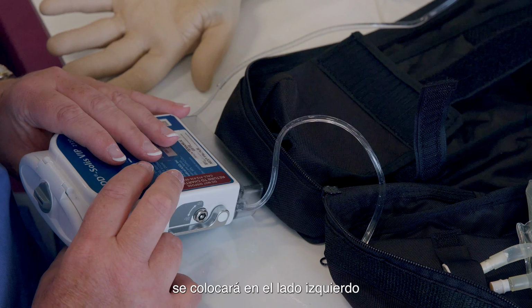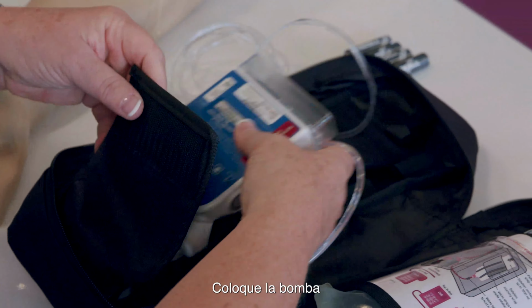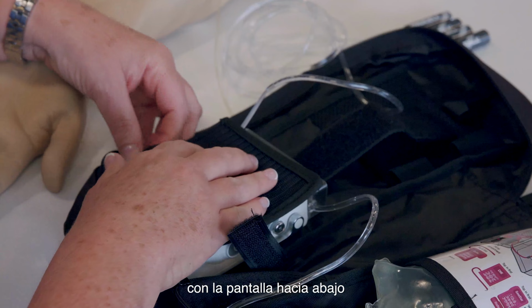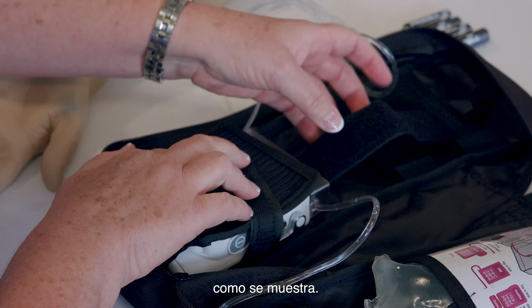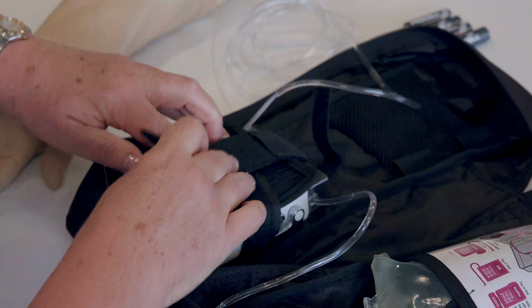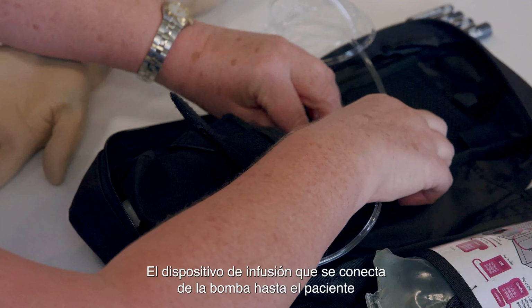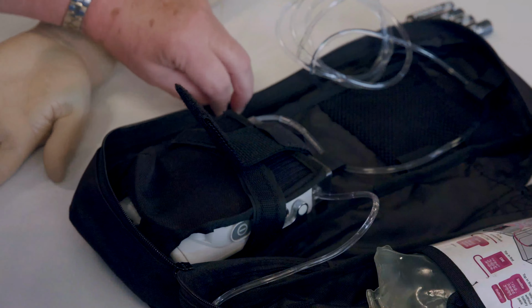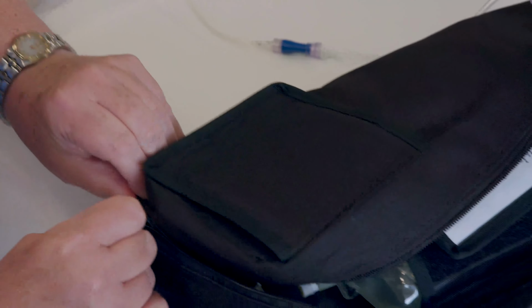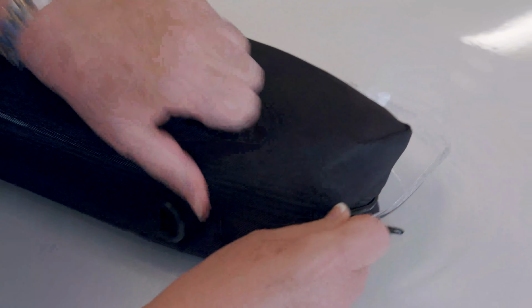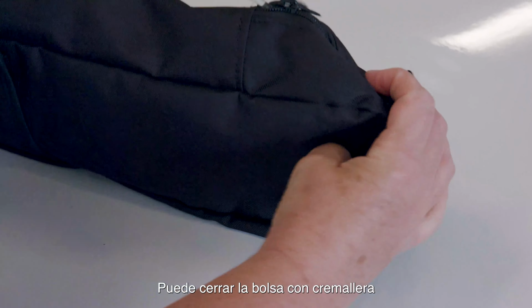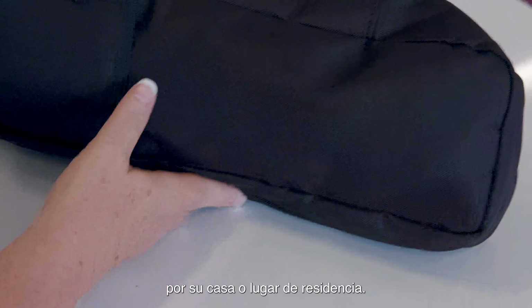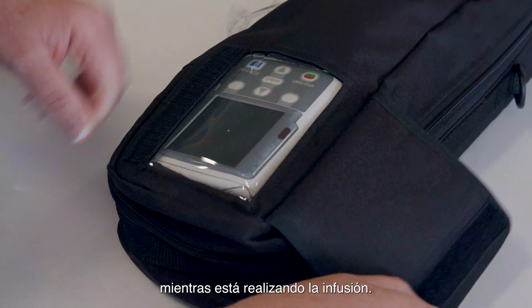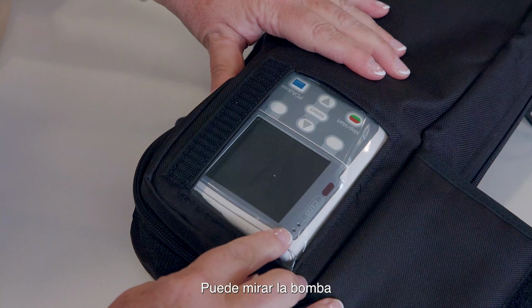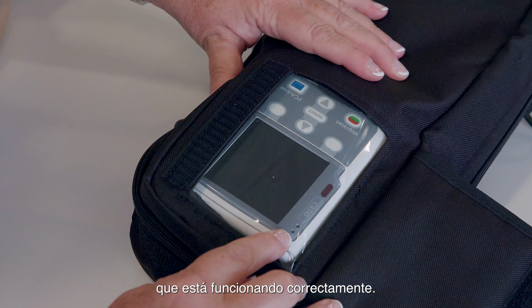The CADD Solis pump will be stored on the left side of the pouch. Slide your pump with the pocket screen side down and secure with a Velcro strap as shown. Tubing from the pump to the patient should be threaded out of the pouch at the zipper opening. The pouch can then be zipped closed and carried with you as you move around your home or community. Always keep your medication pouch near you while it is infusing. You can check on the pump by opening the flap on the pouch to confirm it's running properly.